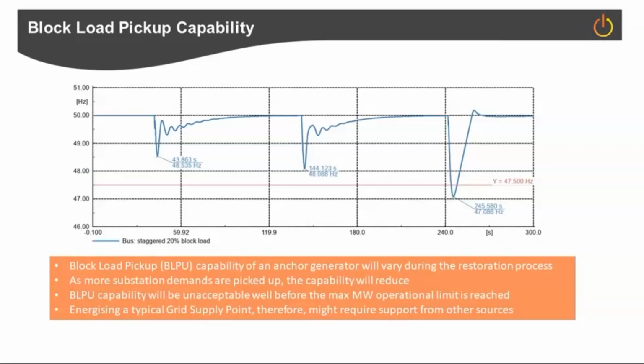Sorry, there's a question that's come through. As more substation demands are picked up, the capability will effectively reduce, and there'll ultimately be a minimum frequency level. I think it's 47.5 hertz is the minimum level of frequency that we're operating to here in GB with regard to block loading capability. So the block loading capability will effectively become unacceptable at a level well below the maximum operational limit of that generator. So that's quite an important point.